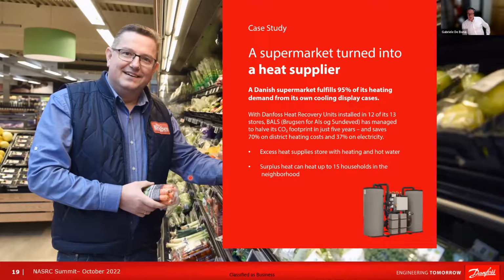This solution has been adopted by a Danish supermarket chain, not a big one, but quite popular in Denmark. And thanks to the adoption of this heat recovery unit, they were able to cover 95% of the total heating need of each single store. And this allowed them to decrease the CO2 footprint of the store, halving it in 5 years, and to save 70% of the cost of the heating and 37% on the electricity itself.